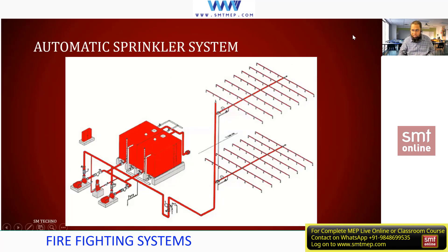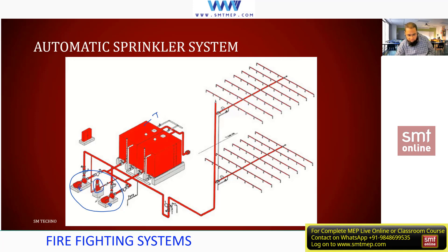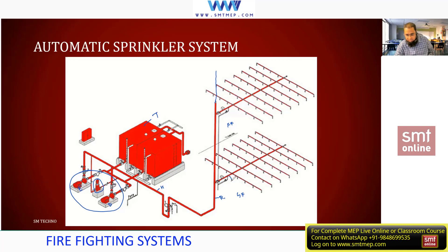Next is the sprinkler system. The detail will be found in NFPA 13 after completing NFPA 10. The components include a tank, pump sets — one electric pump, one diesel pump, and one jockey pump. There is a separate module for pumps under NFPA 20. After the tank and pumps, the main pipe is called the header. The vertical pipe is called the riser, and the horizontal pipe entering each floor is called the cross main.